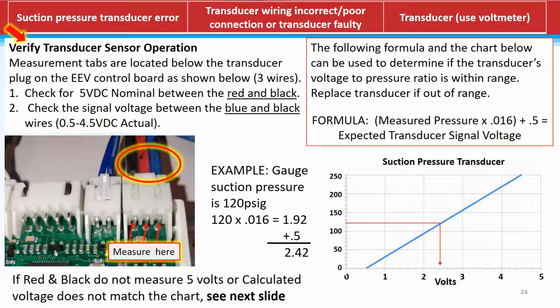Looking to the right of the calculation, you'll see a suction pressure transducer chart with a blue line running from left to right. That's the voltage as the pressure goes up. That's how the curve works for this transducer. You see my red line at 120, going to the right until it connects with the blue line and then straight down. If you look close, you'll see that it lands on 2.42, and this is correct. The transducer is functioning properly. If the transducer is functioning properly, you can skip the next slide.